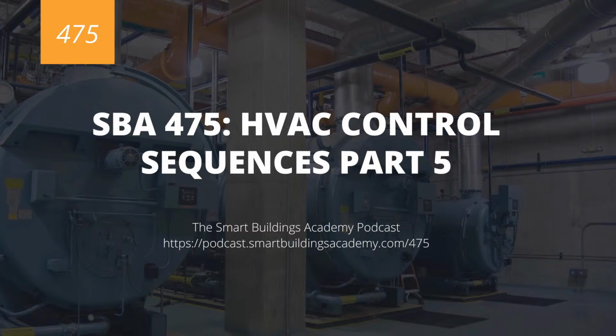Notice this is kind of inferring that there's a lead-lag scenario, which is typical of boilers and chillers, where you have a primary pump that runs as lead, and then you have a lag pump in case that primary pump fails and that lag pump comes on. The lead and lag are both individually sized for the GPM requirements of the boiler or chiller and are rotated either on runtime or based on start count. I prefer runtime. Some folks prefer start count. Runtime, I feel, gives you a more accurate rotation.